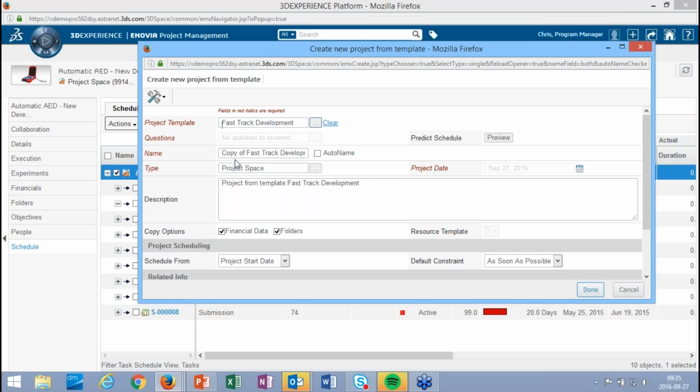And if that's the case, I will have qualifying questions on what's the market to address, what's the regulatory scheme for that particular market, is this a class 1 or class 2 or class 3 product, and if so, what kind of, is it a pre-market approval or a 510K or a technical file or dossier.